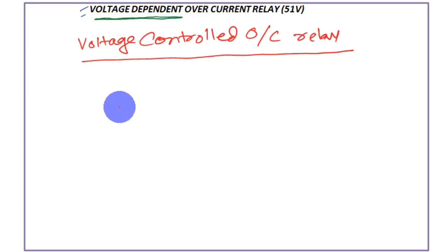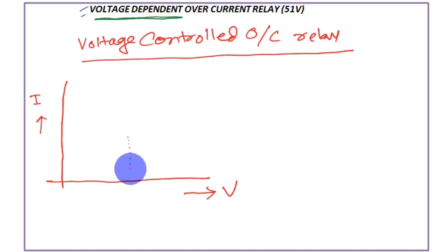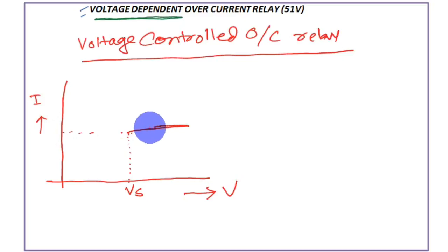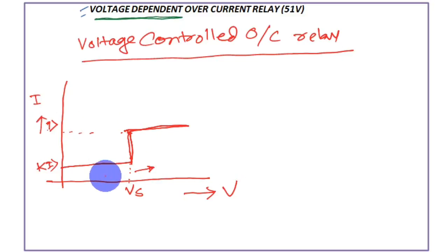Let us draw the pickup characteristics of the voltage controlled overcurrent relay. On the x-axis is voltage and on the y-axis is pickup current I. There is a set voltage point Vs. Above this voltage — when the generator terminal voltage is greater than Vs — the pickup current is higher, set to I_greater_than. Below Vs, the pickup current is reduced to a lower value Ki_greater_than.